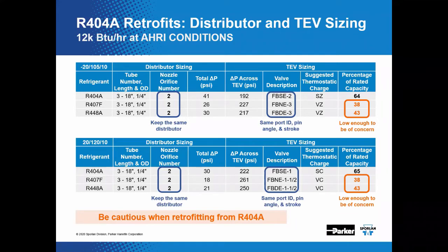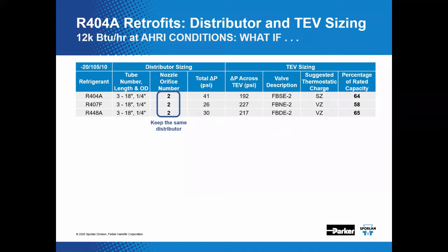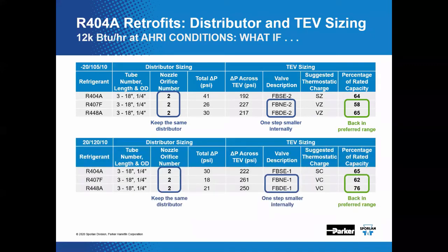Just in conclusion here, for this particular part of the discussion, we need to be cautious when retrofitting from R404A. What if we considered the same low temp system and again kept the same number 2 distributor nozzle, but switched to a TEV that is 1 capacity step smaller? We now have the percent loading back in the preferred range. Does the same thing work on medium temp systems? It appears that it does. So in this example, we can step down 1 size in the thermostatic expansion valve product line and move back into the preferred percent loading range and get the correct thermostatic charge as a bonus.